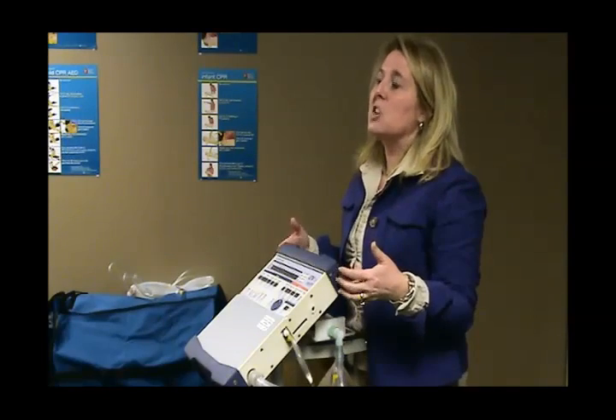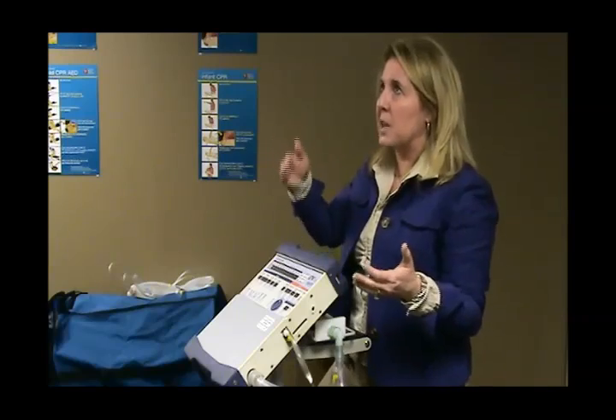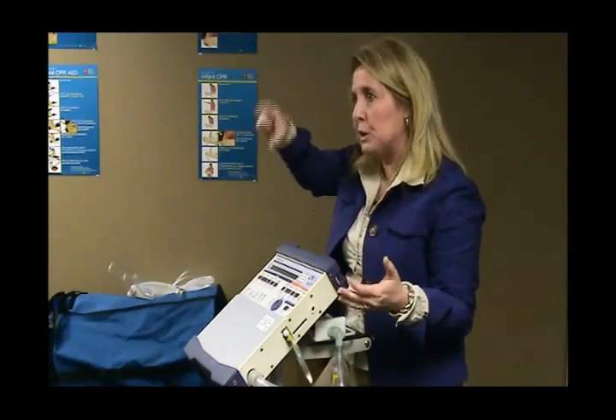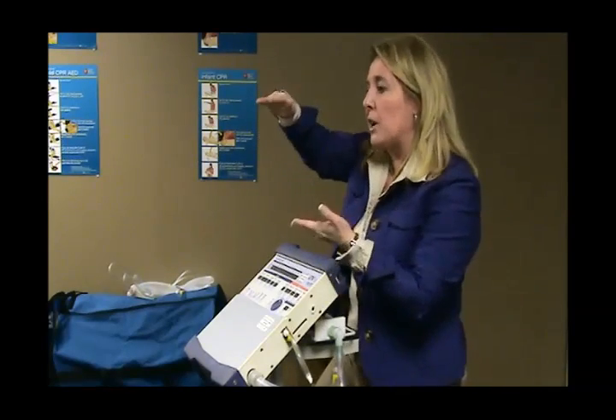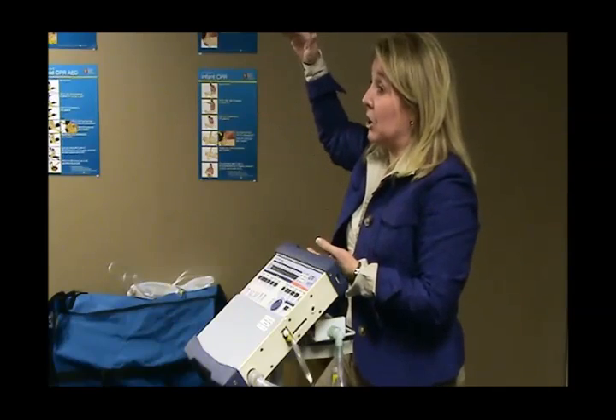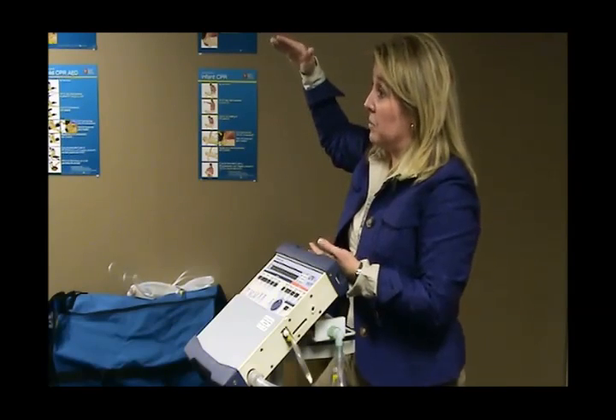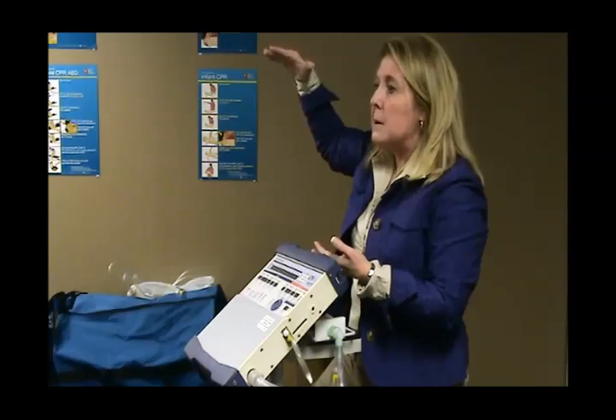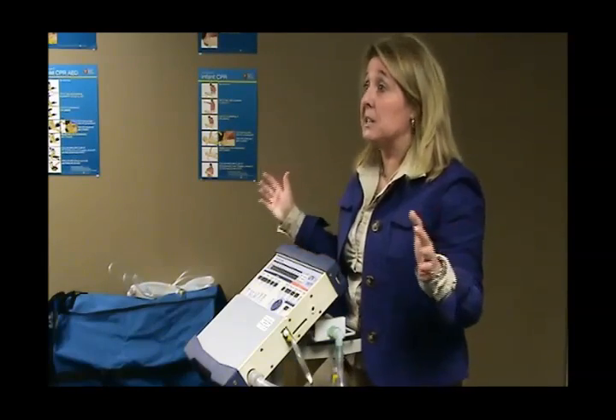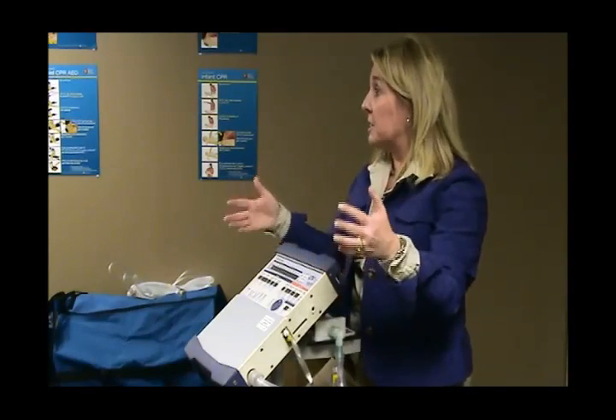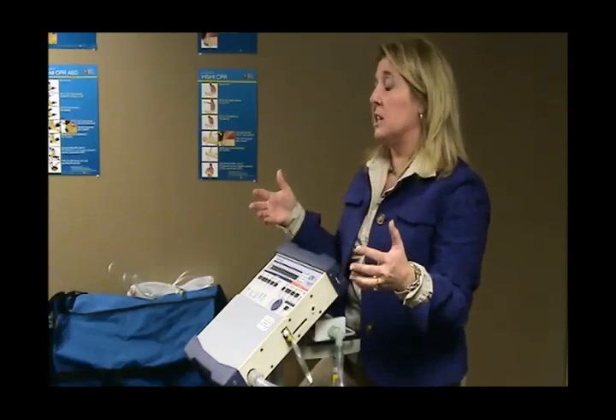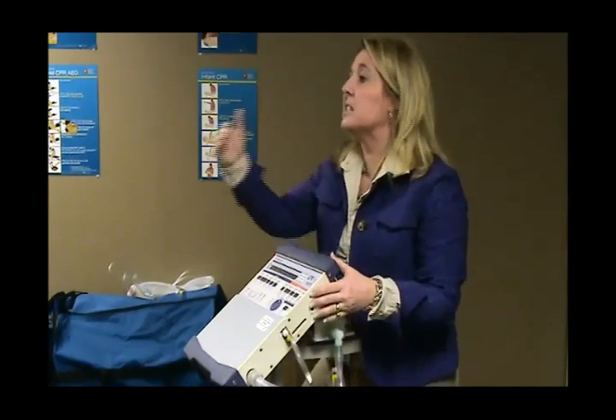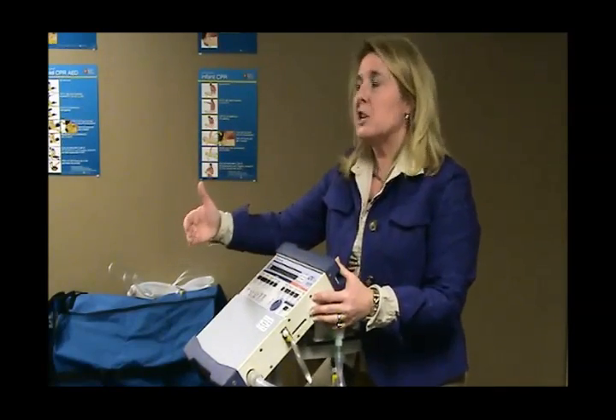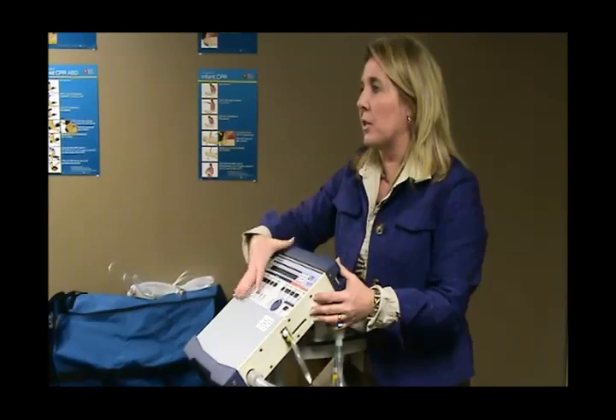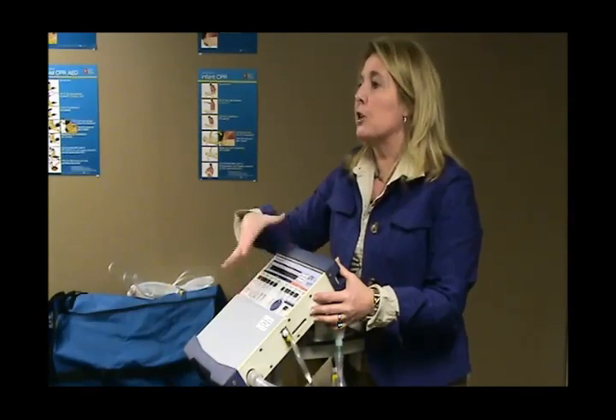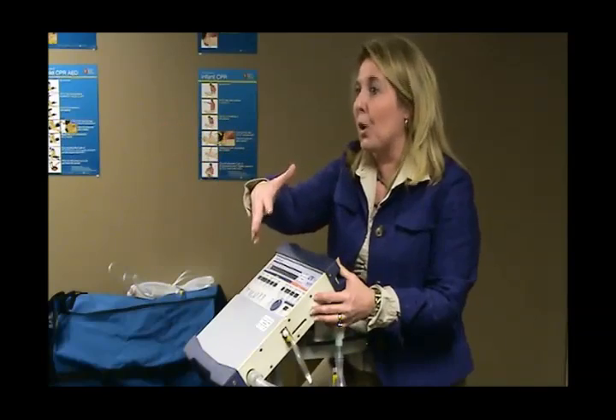And the preventative maintenance on our ventilators is fairly inexpensive. The every 2-year one, and the 4-year, is pretty inexpensive. The 6-year is expensive. It's like $2,000 to get it PM'd. So what I teach my DMEs, and what you guys can help pay attention to, working together with the RTs from the equipment companies, is that if your vent is due for a 6-year PM, they should probably trade that ventilator in and get them on one of the new style ventilators, because they'll spend more on the PM than the ventilator's worth.